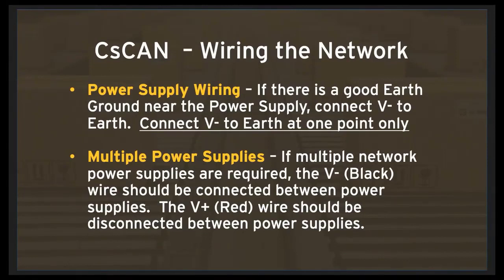So, compared with the other topics, we spent quite a bit of time talking about power draw and voltage drop. Now, keep in mind that for most CsCAN applications, you're going to be below 30 meters, you're going to be below 4 or 5 I/O nodes, so none of those calculations will be required. But again, I want to give you the tools so that if you do take advantage of this great capability of CsCAN for longer networks and more nodes, you'll know how to do it.